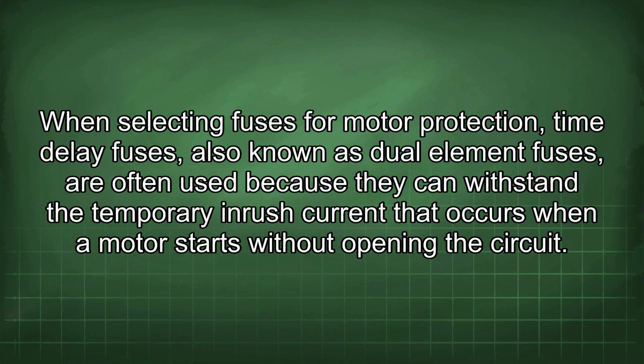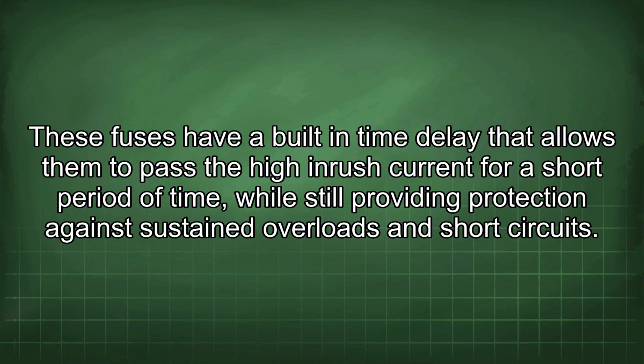When selecting fuses for motor protection, time delay fuses, also known as dual element fuses, are often used because they can withstand the temporary inrush current that occurs when a motor starts without opening the circuit. These fuses have a built-in time delay that allows them to pass the high inrush current for a short period of time, while still providing protection against sustained overloads and short circuits.